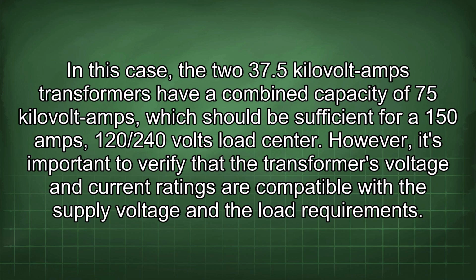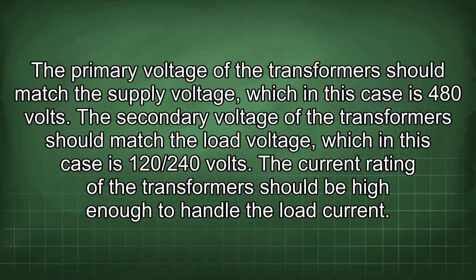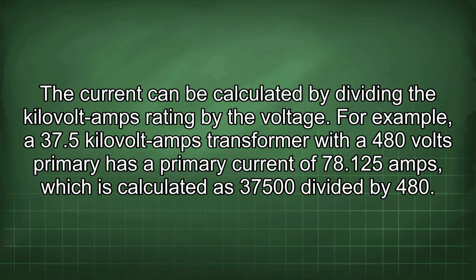However, it's important to verify that the transformer's voltage and current ratings are compatible with the supply voltage and the load requirements. The primary voltage of the transformer should match the supply voltage, which in this case is 480 volts. The secondary voltage of the transformer should match the load voltage, which in this case is 120/240 volts. The current rating of the transformer should be high enough to handle the load current.